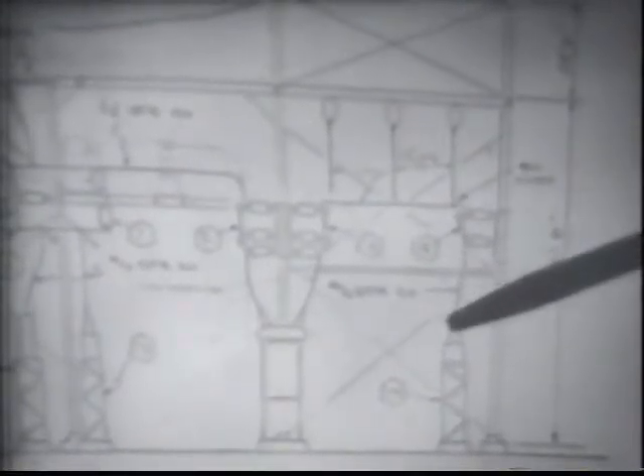substation. This structure here is what's called the continuous frame structure made out of beams. As you can see, we have a line coming in here, dead ending on this truss right here. This would be the insulators. From the incoming line, we step down to a bus conductor that's supported by these bus supports right here. It goes over to this disconnect switch, comes down through the circuit breaker, up through another disconnect switch, and then is connected to a bus support here. In turn, we tap off at this point through a fuse to a potential transformer.